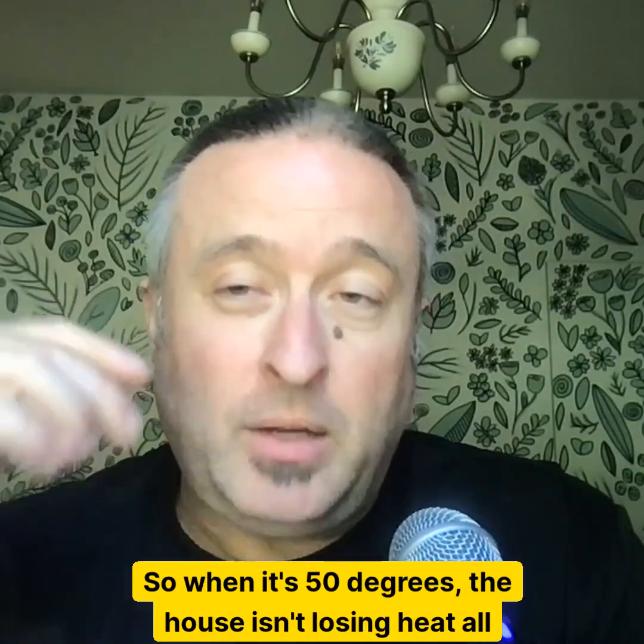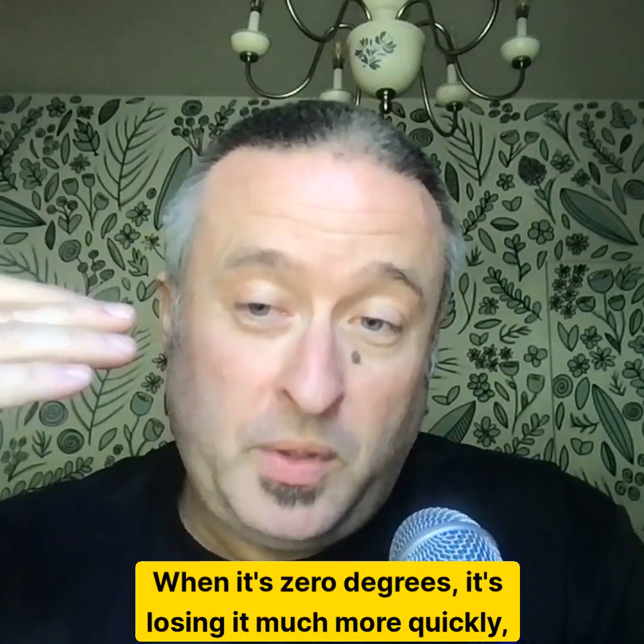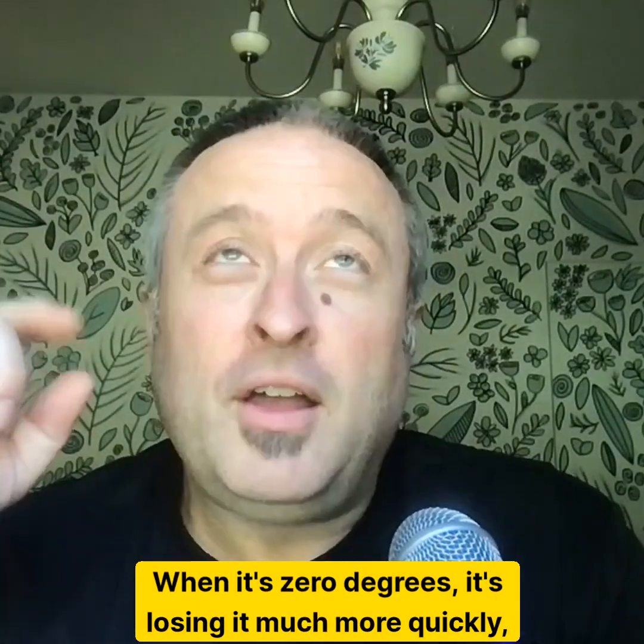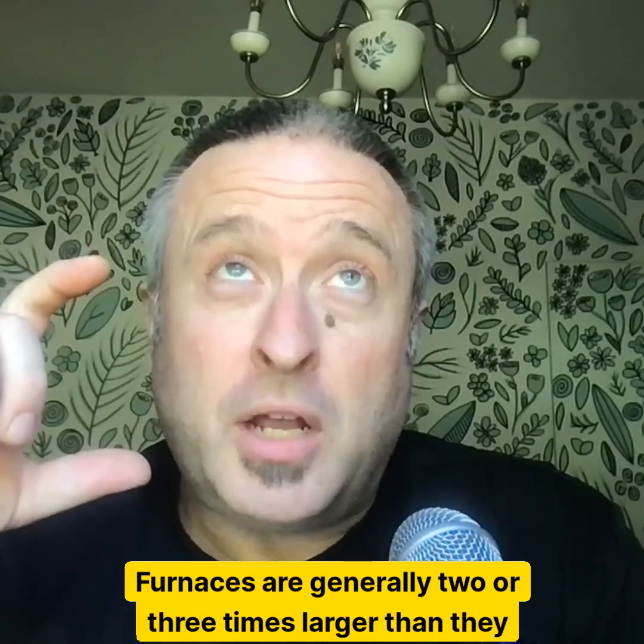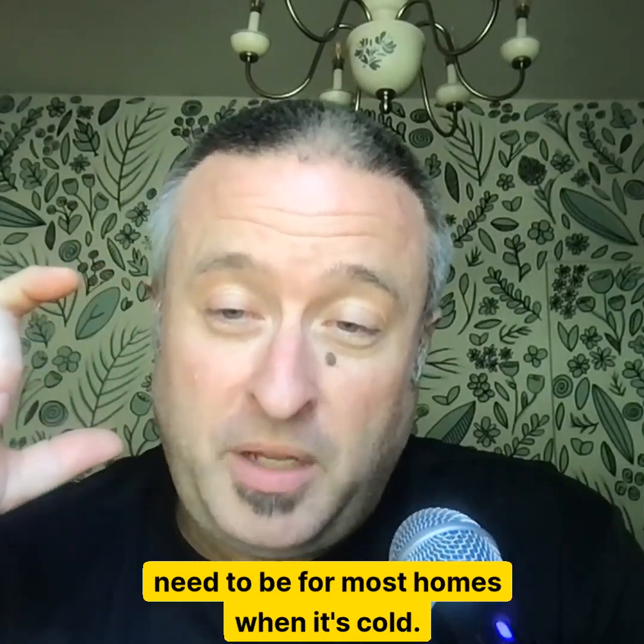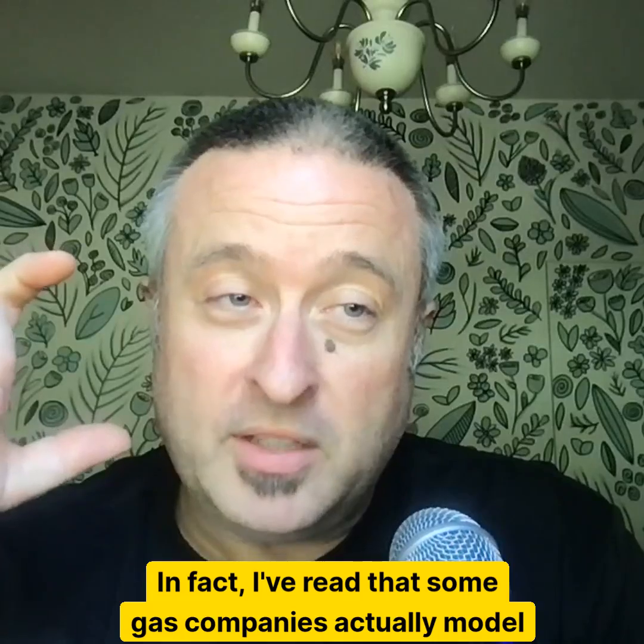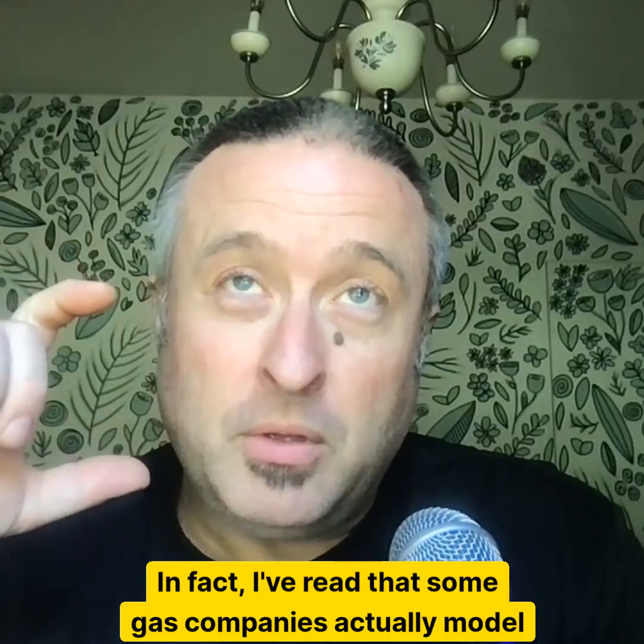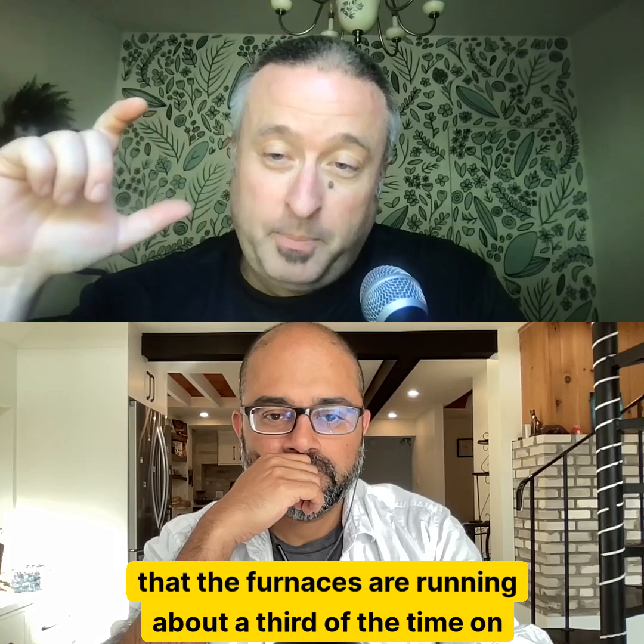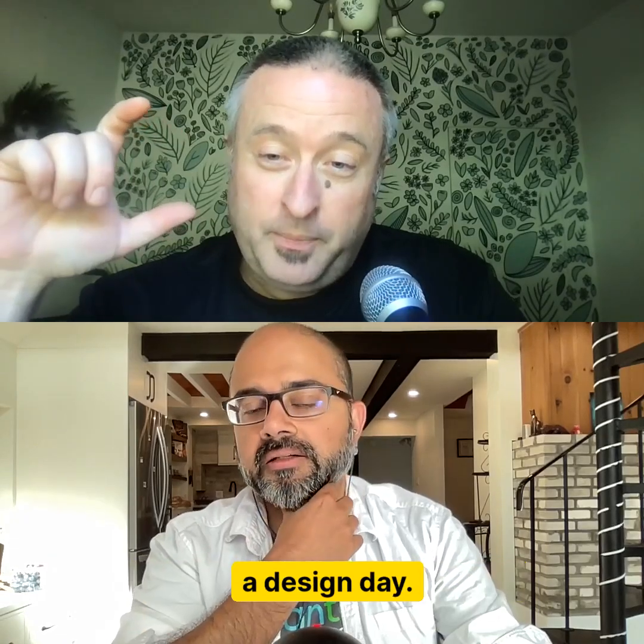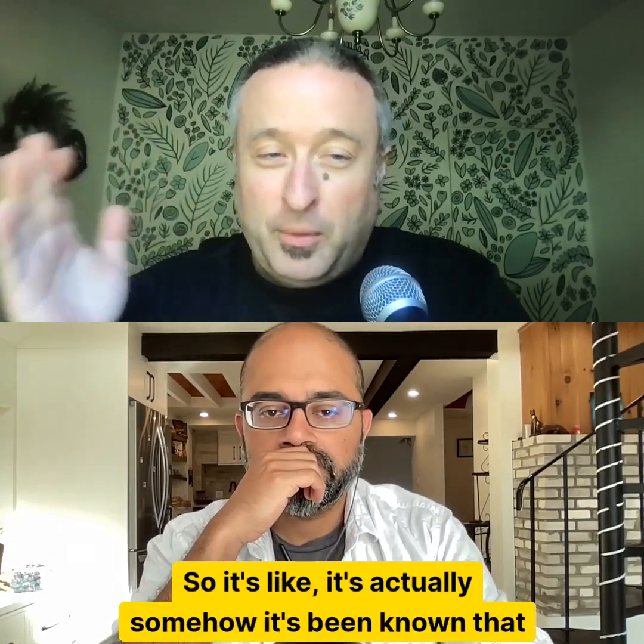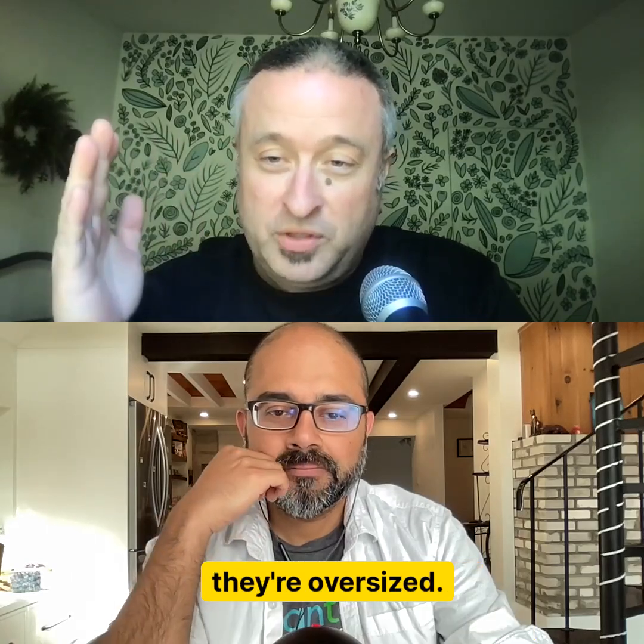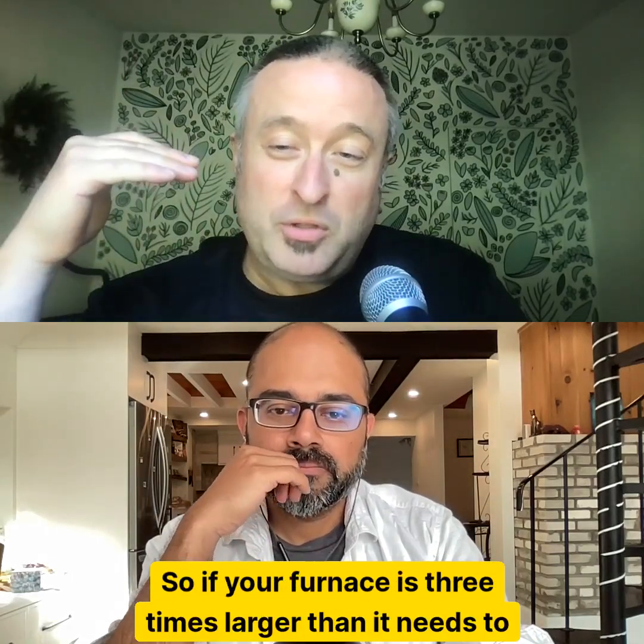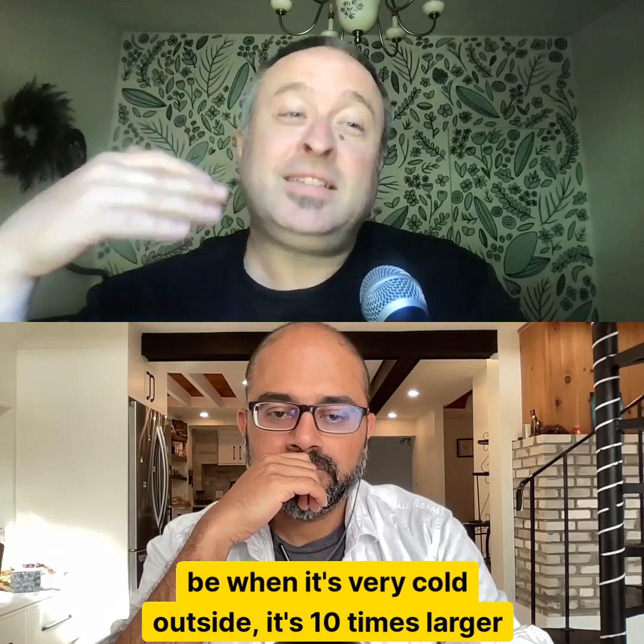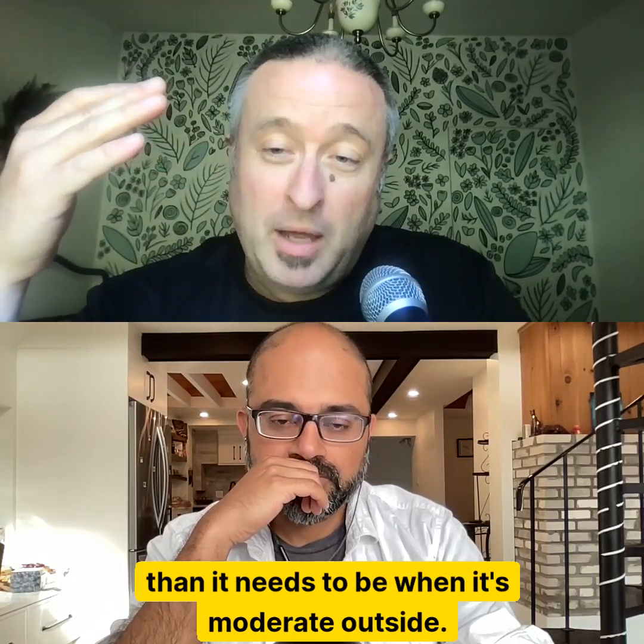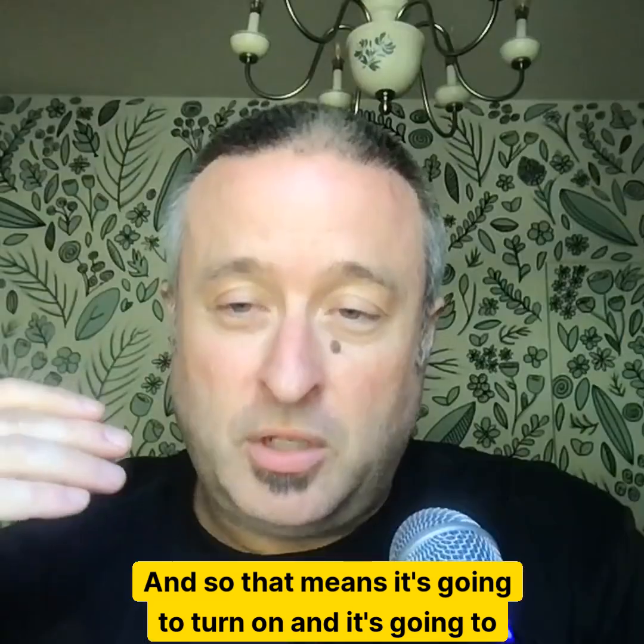When it's 50 degrees, the house isn't losing heat all that quickly. When it's 0 degrees, it's losing it much more quickly. Furnaces are generally 2 or 3 times larger than they need to be for most homes when it's cold. In fact, I've read that some gas companies model that furnaces are running about a third of the time on a design day—so it's actually somehow known that they're oversized. If your furnace is 3 times larger than it needs to be when it's very cold outside, it's 10 times larger than it needs to be when it's moderate outside.